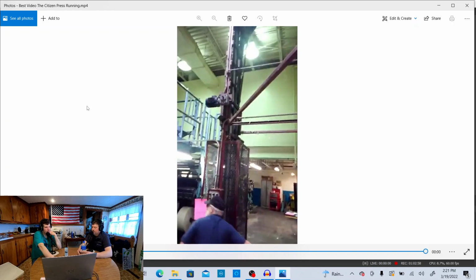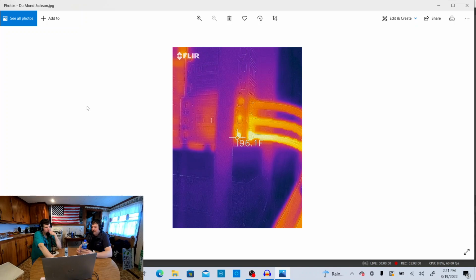That's a screenshot I took of a breaker that was overheating and tripping, and I found a loose connection. The copper was discolored, so I had to take it off, recut it, and put it back in, cranking it down tight. The bolt holding the lug on the breaker was loose too, so I had to pull the breaker out and tighten everything up inside it.